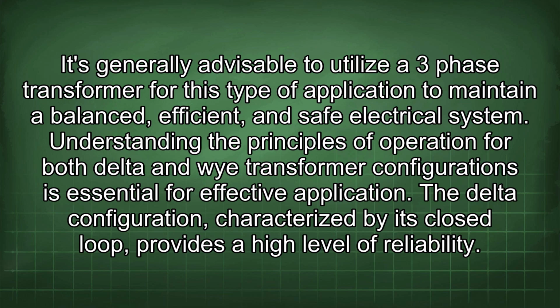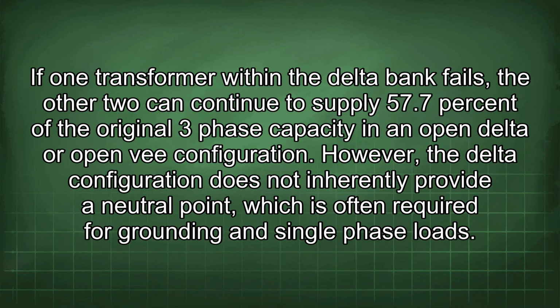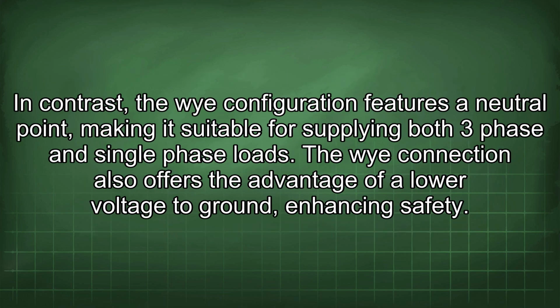The delta configuration, characterized by its closed loop, provides a high level of reliability. If one transformer within the delta bank fails, the other two can continue to supply 57.7% of the original three-phase capacity in an open delta or open V configuration. However, the delta configuration does not inherently provide a neutral point, which is often required for grounding and single-phase loads. In contrast, the Y configuration features a neutral point, making it suitable for supplying both three-phase and single-phase loads. The Y connection also offers the advantage of a lower voltage to ground, enhancing safety.